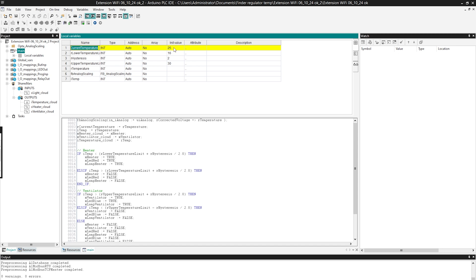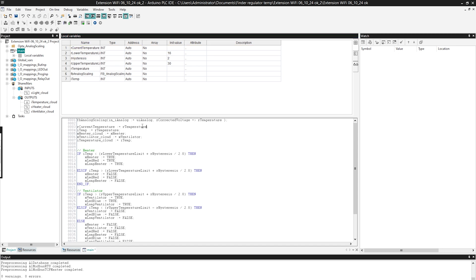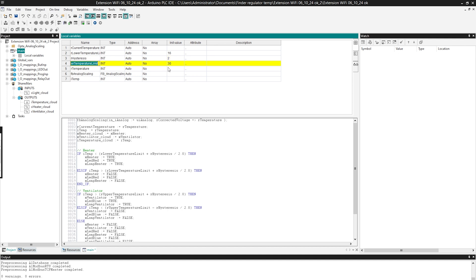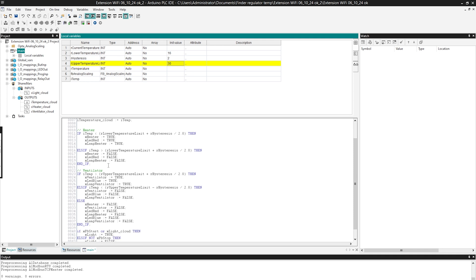The current temperature is taken from the temperature sensor. Then we have the lower limit at which the heater turns on, which is 16 degrees Celsius. A hysteresis of 2 degrees Celsius, and then we have a certain hysteresis for turning on the heater. The upper limit is 30 degrees Celsius. Based on this I can perform such regulation.